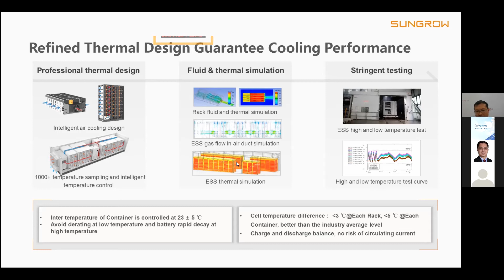With our design, we can guarantee the internal temperature of the container is 23 plus or minus 5. We also can guarantee the battery cell temperature difference is less than 3, and the rack difference is less than 5. So with this design, the temperature mismatch between each battery module and battery rack is very low. Low mismatch means we can discharge more energy.